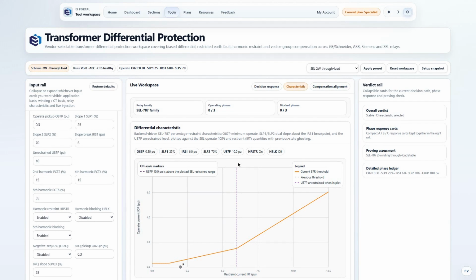And before anyone assumes this is preset wear, watch. Every value on the rail is yours to set. Take the first slope from 25 to 40% and the characteristic steepens in front of you, leaving the ghost of the old curve behind for comparison. It's your relay, your settings, and your scheme. Let's put it back to factory and carry on.